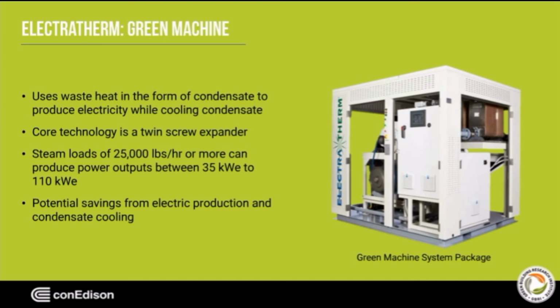The last technology I want to speak with you today about is from a company known as ELECTRATHERM. ELECTRATHERM designs and manufactures systems known as the Green Machine, which generate fuel-free, emission-free electricity from low-grade waste heat into power. ELECTRATHERM also utilizes a twin screw expander as the power block for the system. Unlike the other four technologies that I have just spoken about that work in parallel to a pressure reduction valve, this system works by utilizing condensate.